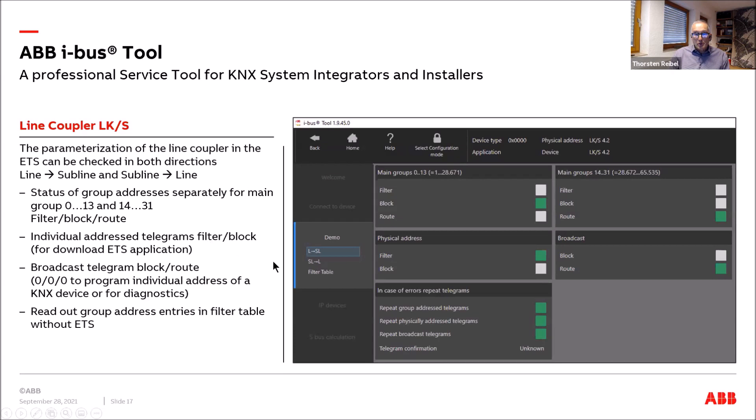For the line coupler, there is nothing to operate — it is purely diagnostic. You can see the status of group addresses and whether they are programmed as filtered, blocked, or routed. The same applies for individual address telegrams needed for ETS application download and broadcast telegrams used for programming the individual address. You can also view the full filter table programmed in the ETS.